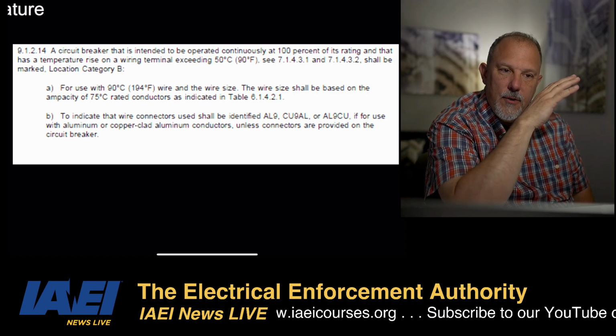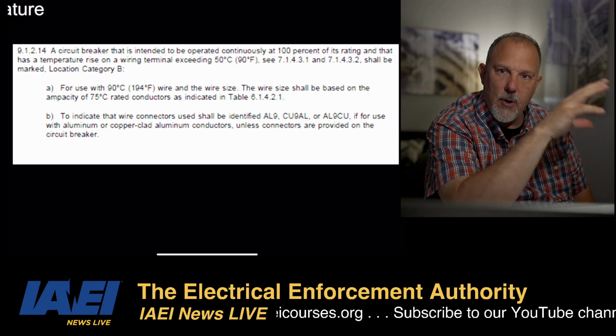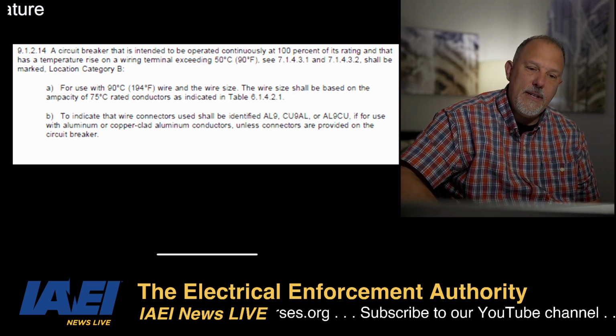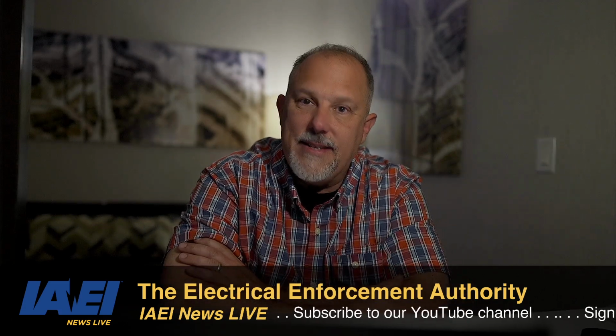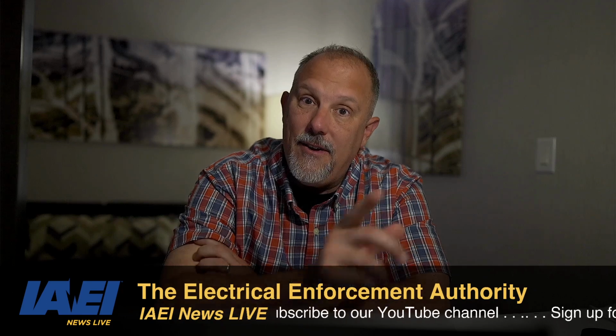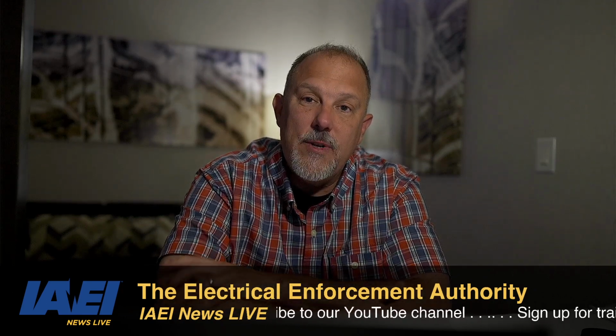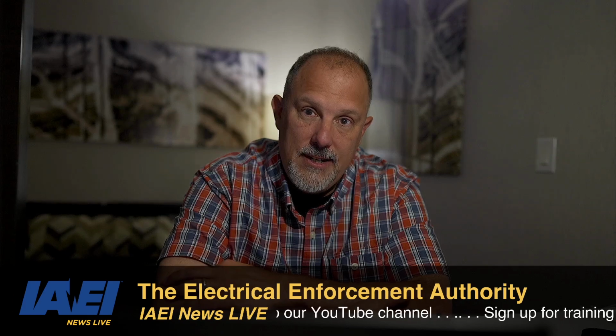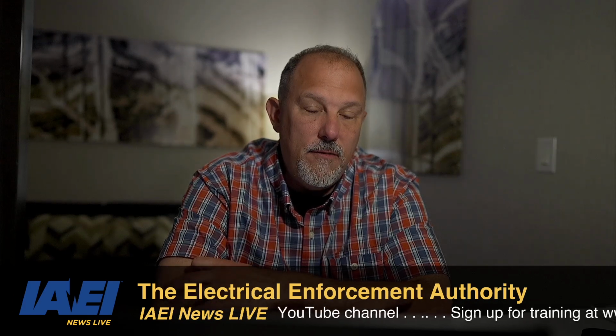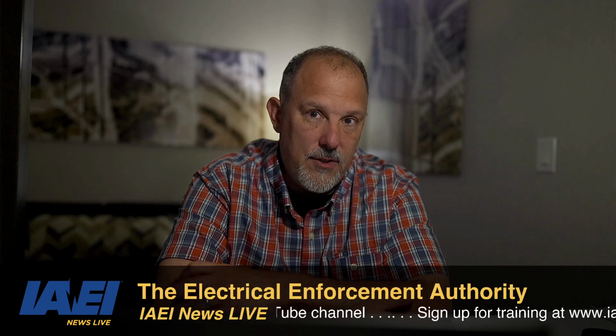So temperature ratings and markings on these devices, on circuit breakers, are going to be driven by the standards. Now, it wasn't until the 2023 code cycle that circuit breakers, low voltage circuit breakers, and fuses were required to be listed. Chew on that one for a little bit.